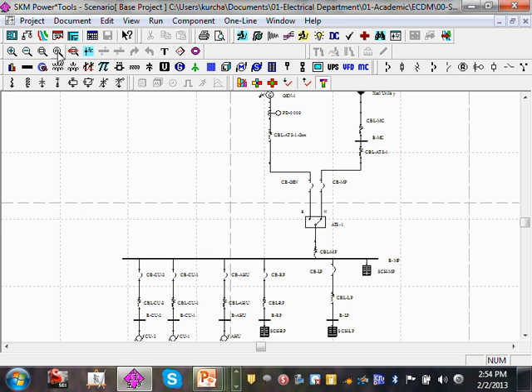Into this system, we happen to have an auto transfer switch with a generator here. So here's my gen. I have my cables coming to a circuit breaker, 2 circuit breakers. This is my service for the utility. This is my disconnect for the generator. Through an auto transfer switch down to my panel. Very simple system. In a case like this, I don't know how many people have done an auto transfer switch that's rated for service entrance. They sell them. You have to have 2 circuit breakers, basically an auto transfer switch, or they use 2 circuit breakers as the auto transfer switch. Okay, so we came over here, and then all these are impedances into the system down into my equipment right at the bottom here and my bunch of panels here.